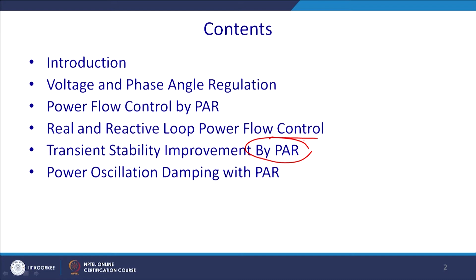So, why do we choose the phase angle regulator? Essentially you know that sending end voltage times receiving end voltage divided by X into sine delta is the power sent through the transmission line. You can increase the sending end power by changing the voltage V1 or V2 or X, as we have seen in the case of series compensation. But we can also do the same thing by changing the angle delta, and thus power can be enhanced or decreased as you wish, without touching other parameters like V1, V2 and X.